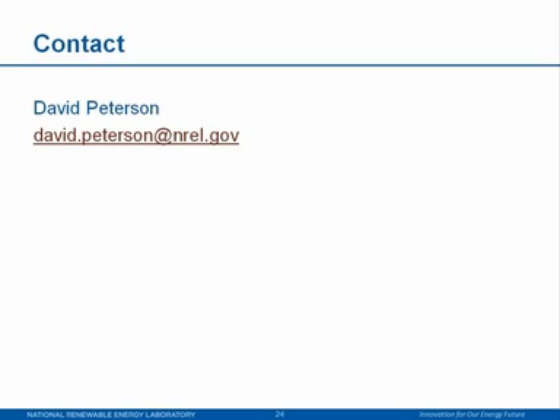Great, thank you. Under what conditions should you never install a ground source heat pump? One of the main things is asking whether wherever you're putting the loop field will ever be needed for some other purpose. If you have a plot of land next to you that you might want to sell at some point, don't put your loop field there, because someone may want to excavate it. So it's really about where you're putting your loop field. These systems have probably been installed in every state, but they tend to work better where soil conditions are best suited for a ground source heat pump system. I'd say never install one when you don't know the future of the space or land where you're putting your loop field.